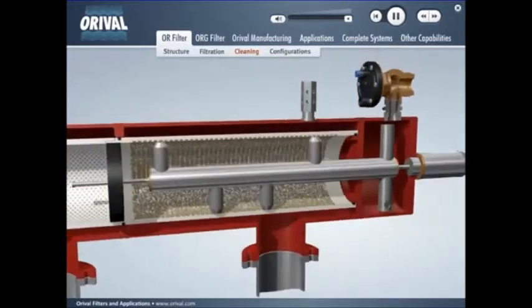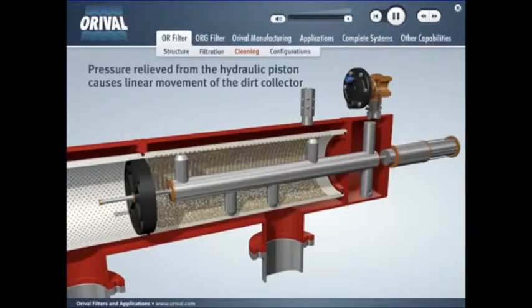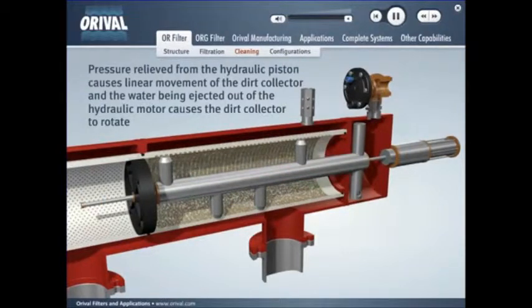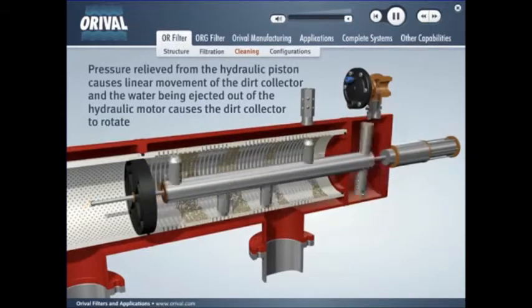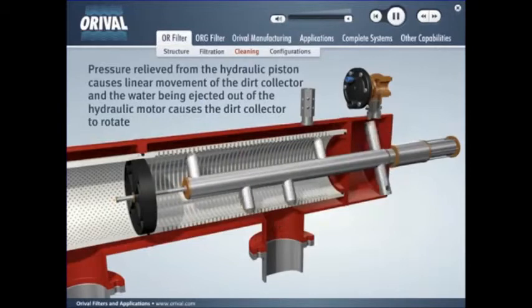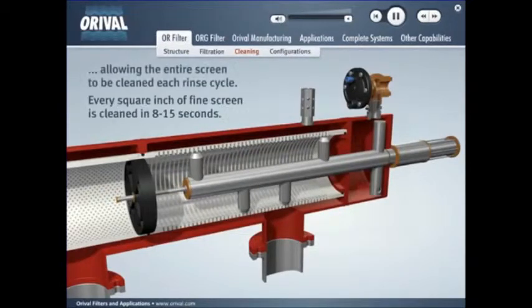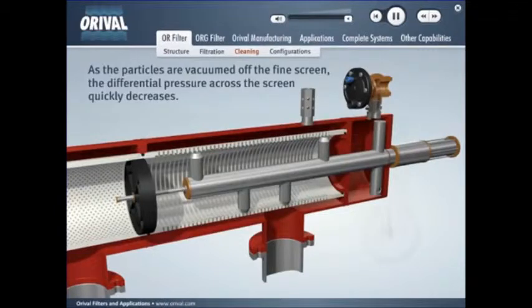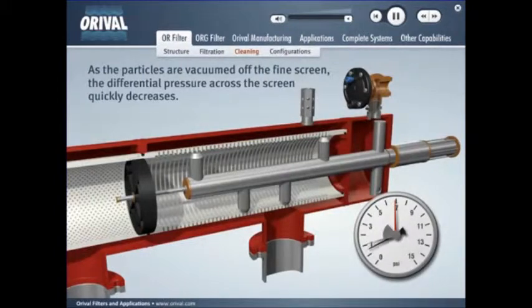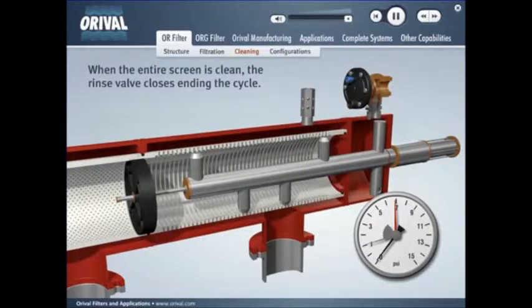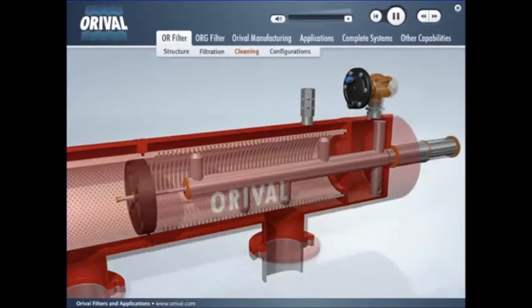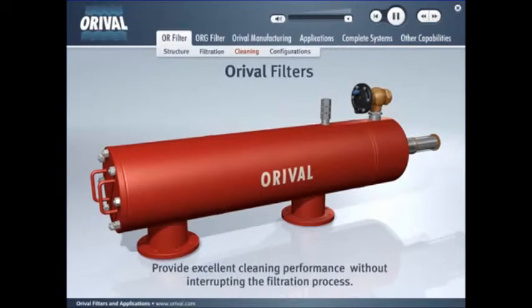Pressure relieved from the hydraulic piston causes linear movement of the dirt collector, while the water being ejected out of the hydraulic motor causes the dirt collector to rotate, assuring that the entire screen is cleaned during each rinse cycle. Every square inch of the fine screen is cleaned in 8 to 15 seconds, depending on filter model. As the particles are vacuumed off the fine screen, the differential pressure quickly decreases. When the entire screen is clean, the rinse valve closes, ending the cycle. Orival filters provide excellent cleaning performance without interrupting the filtering process.